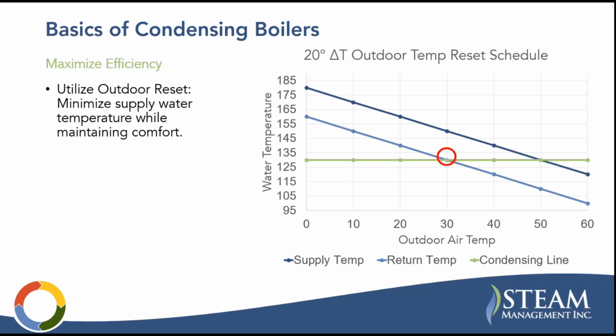This is one way, and the most common way I would say to retrofit, which is to make sure that you're using an outdoor reset controller. The idea here is that the set point of your supply temperature to your system modulates based on your outdoor air temperature. You can see on the x-axis, this is outdoor air temperature. On your y-axis is water temperature. The blue line here is your supply temperature, so what your supply is set to. We're assuming a 20-degree delta T, and so this light blue line is your return temperature.